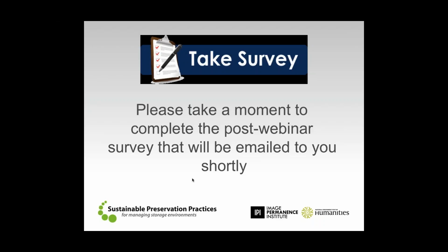And by and large, we haven't seen any instances in normal library archive scenarios where reduction in outside air has caused damage due to increased concentration of pollutants. So that's a longer conversation. I realize that might not have been the clearest answer. There's a lot going on there. But it's a good question, and one that I think that our traditional assumption of the amount of off-gassing is bad and therefore we have to use a lot of outside air to turn over the air and exchange the air is more and more being proven to be untrue.